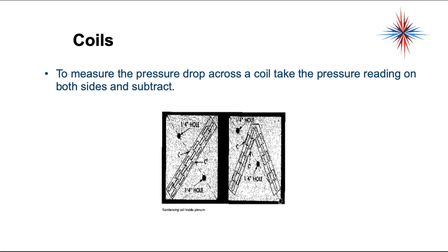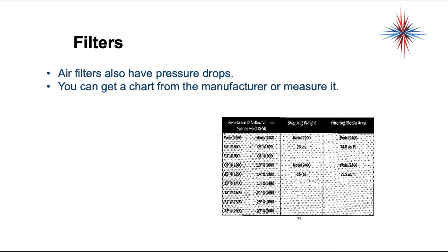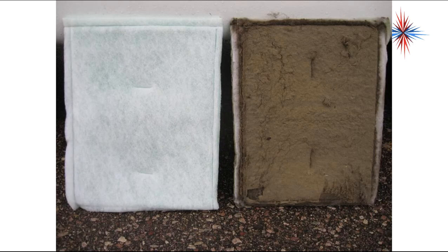Be very cautious when making holes in the ductwork around coils — do not drill into the coil. Be very sure where you're drilling. Filters also have a pressure drop. You can get the chart from the manufacturers or you can measure it. Every filter has a pressure drop, and it will be different based on whether the filter is new and clean or old and used. A new filter will have quite a different pressure drop than a dirty filter.